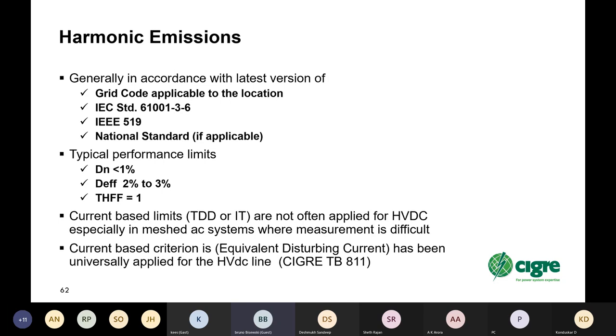Current-based limits, such as total demand distortion or IT, are not often applied for HVDC, especially in mesh systems where measurements are difficult to do. With one exception, the current-based criterion, equivalent disturbing current, has been, up until this date, universally applied for HVDC line interference and telephone interference evaluation. That's discussed in a new CIGRE technical brochure 811, a very large, brand new brochure, which you can refer to when you're looking at telephone interference from DC lines.